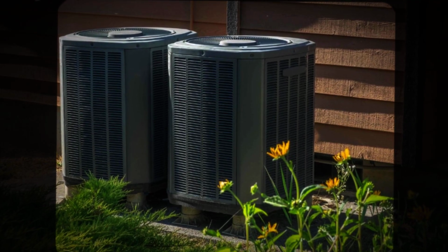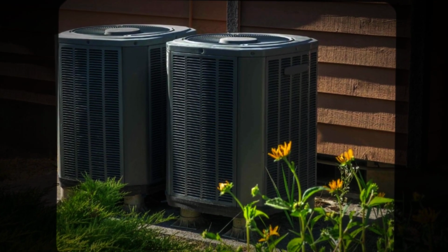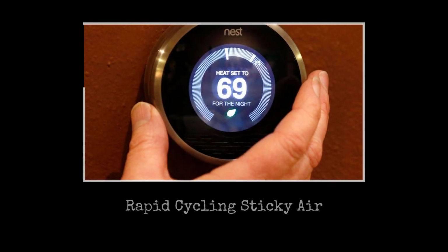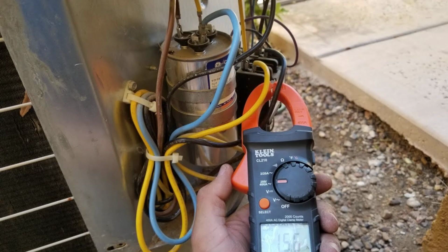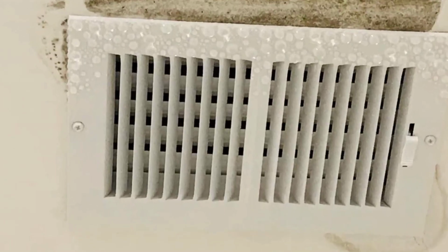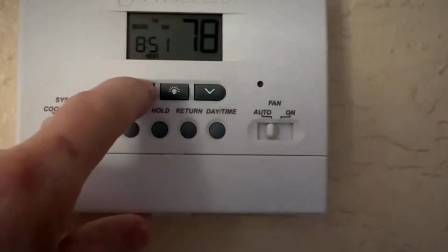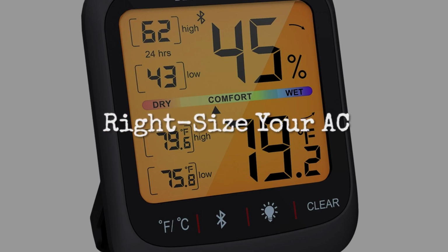It is a trap. An oversized system short cycles, blasts cold air, hits temperature, shuts off, over and over. Every startup hammers the compressor with 5 to 7 times its running current. And here's the hidden problem. It doesn't run long enough to dehumidify. It cools the air but leaves the moisture. So you set the thermostat to 72 to feel comfortable when 76 should be enough.